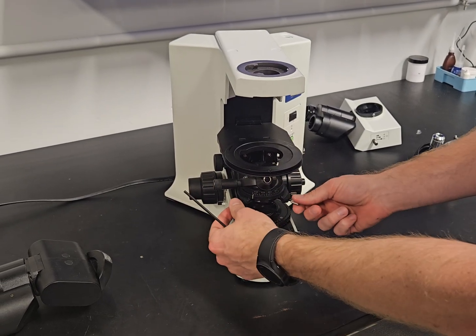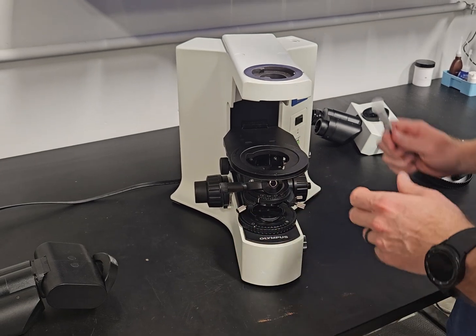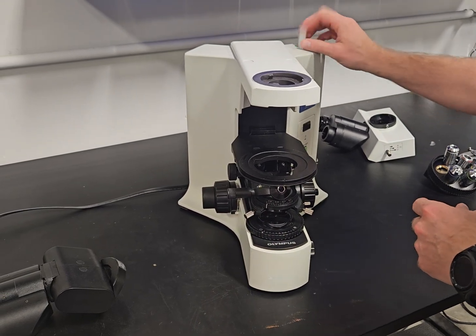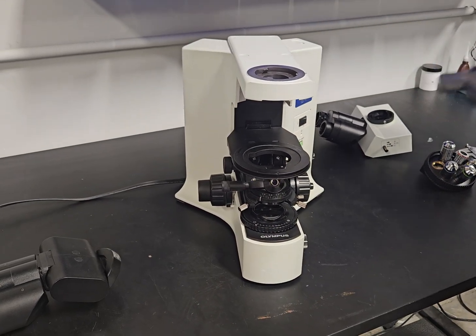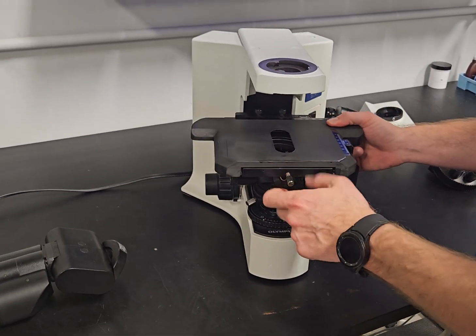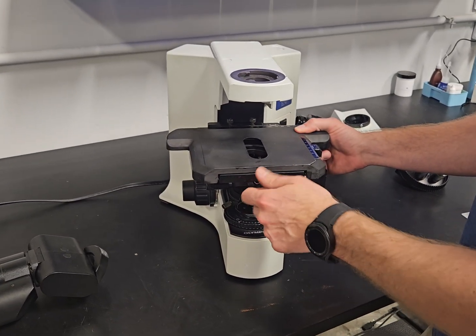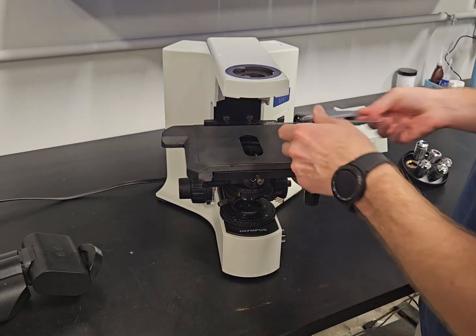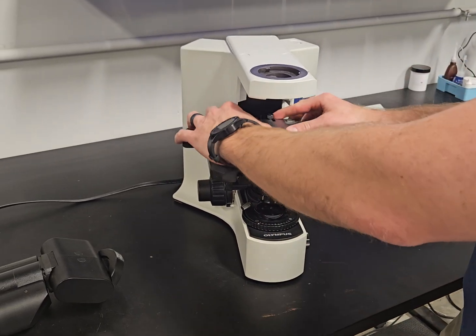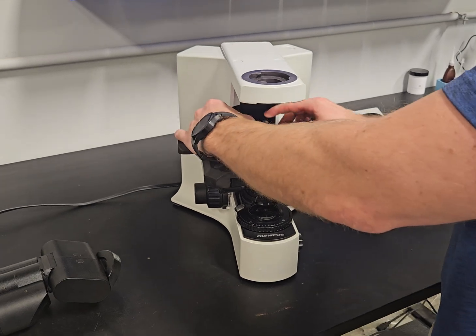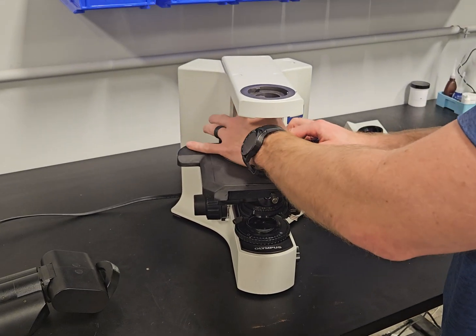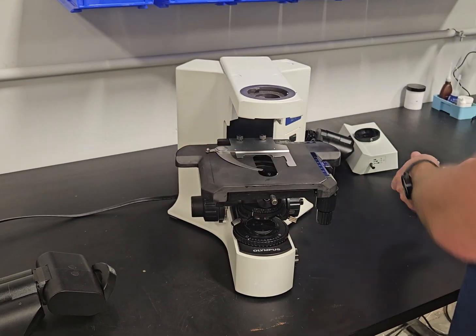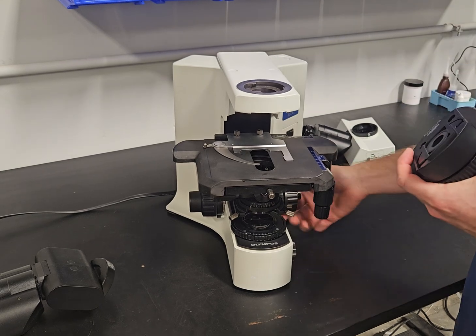These two knobs right here are going to center the condenser. We have another video about setting Köhler illumination that we'll put in the description of this one. It can help you set the Köhler. But whenever you do that, what it's going to do is make sure when you do that process that the scope is par focal from objective to objective within a quarter of a turn is factory spec.